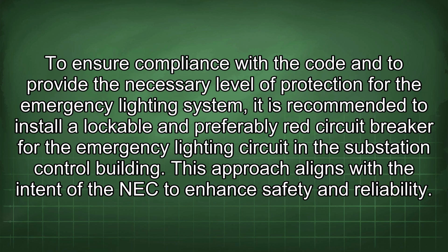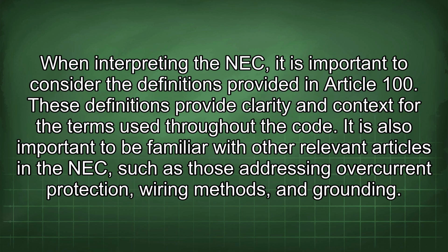To ensure compliance with the code and to provide the necessary level of protection for the emergency lighting system, it is recommended to install a lockable and preferably red circuit breaker for the emergency lighting circuit in the substation control building. This approach aligns with the intent of the NEC to enhance safety and reliability. When interpreting the NEC, it is important to consider the definitions provided in Article 100. These definitions provide clarity and context for the terms used throughout the code.